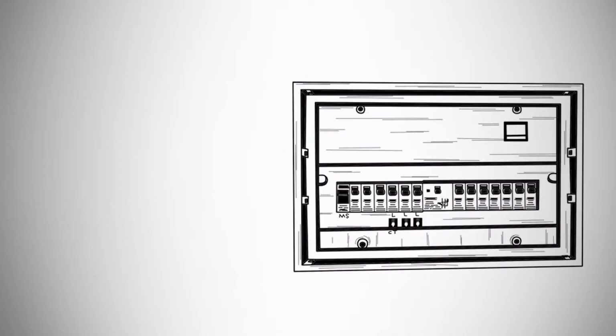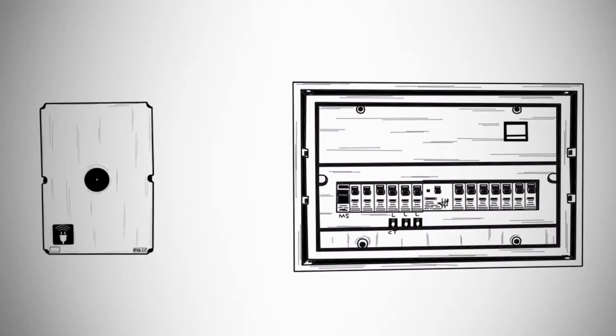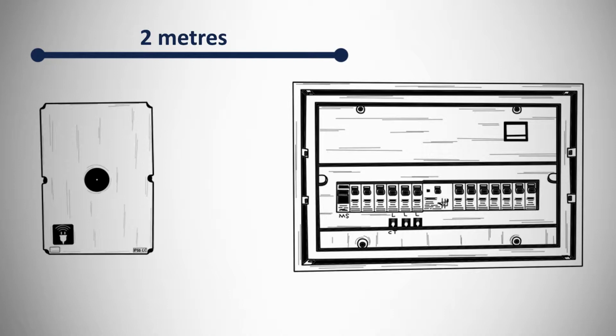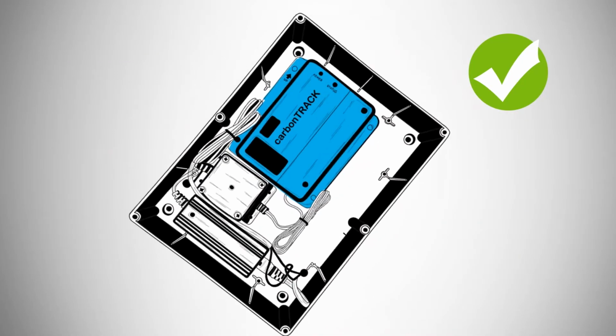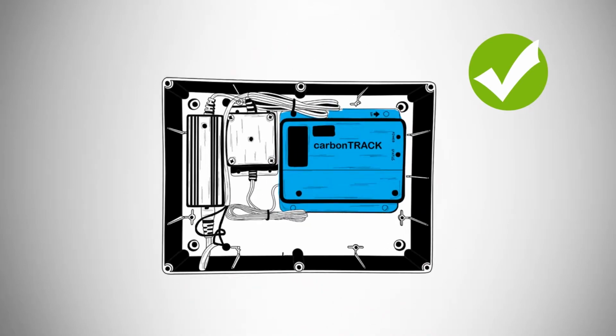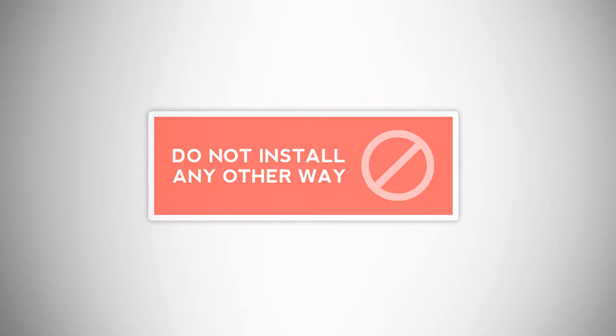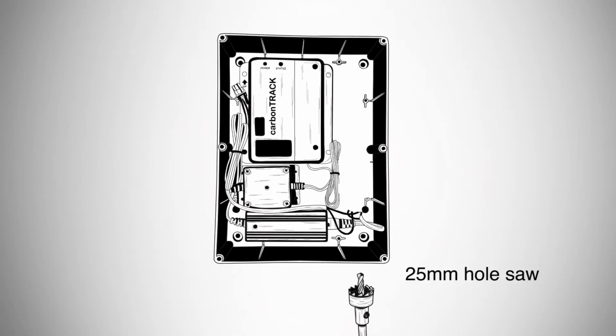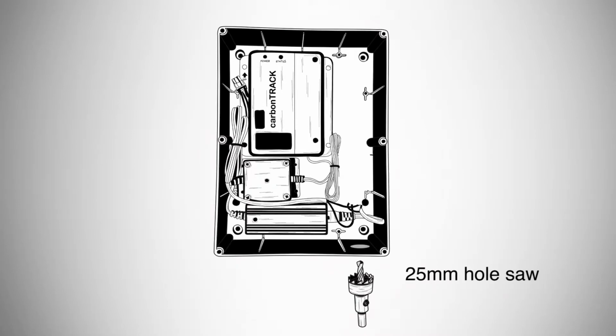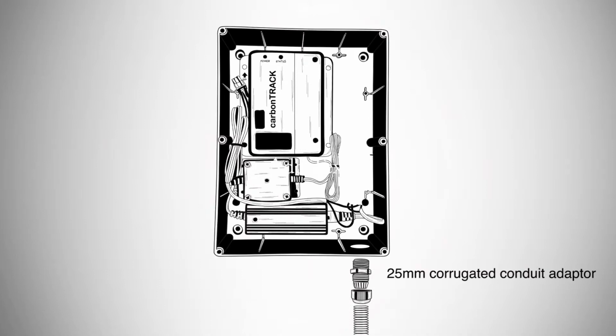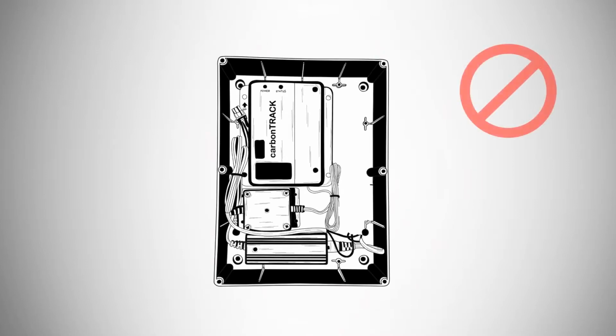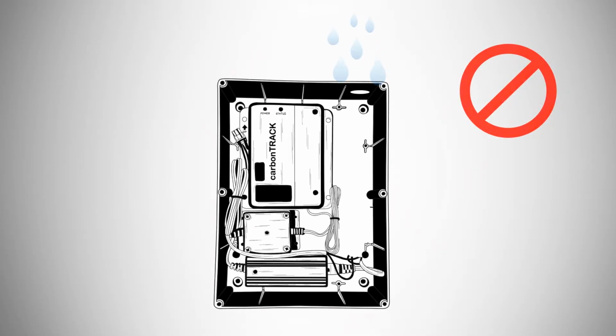The first step in the installation is to find a suitable mounting location within 2 meters of the electrical distribution board. The unit must be installed upright or on its side, with the CT unit in the top right corner position. Do not install any other way. Use a 25mm hole saw to cut a cable access hole in one of the enclosure walls. Fit a 25mm corrugated conduit adapter if necessary. If installing outdoors, do not drill in a top-facing wall to avoid water getting in.